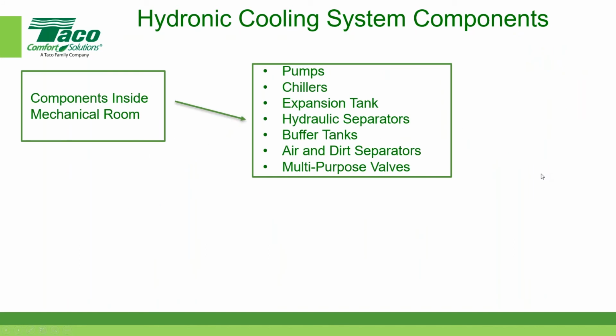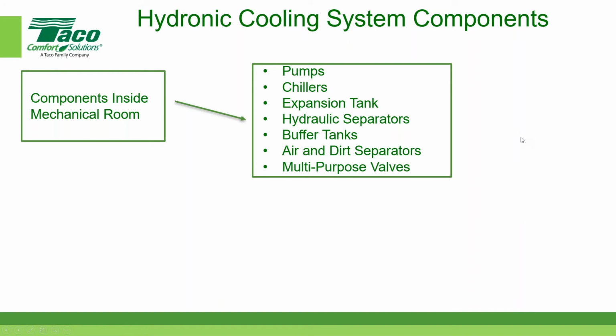Okay, so components that are inside the mechanical room would include pumps and chillers, expansion tanks, hydraulic separators, buffer tanks, air and dirt separators, multi-purpose valves. There's a bunch of other stuff in mechanical rooms like isolation valves and drain valves and all kinds of fun stuff. But tonight we're interested in the major components of a hydronic cooling system. So let's go through each one of these. Pumps is the first one on the list. I like pumps.